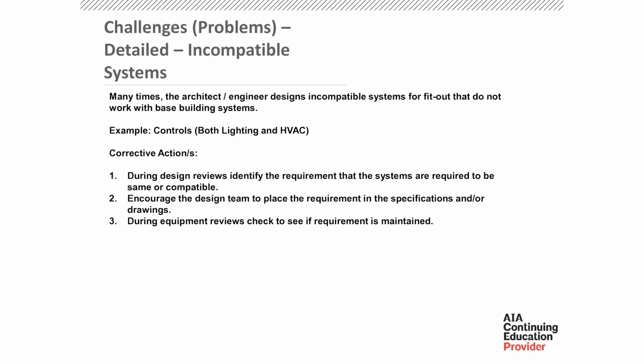Many times the architect/engineer designs incompatible systems for fit out that do not work with the base building systems. For example, both lighting and HVAC: during design reviews, you can identify the systems that are required and compatible. There might be a certain protocol, BACnet versus Lon versus Modbus, and they're not compatible between the two. You might need gateways and everything else to go through that. Encourage the design team to place the requirement in specifications and drawings. During equipment reviews, check to see if the requirement is maintained. So you just check and see if everything's compatible throughout the process, and you try to do it through the design reviews and the equipment reviews.